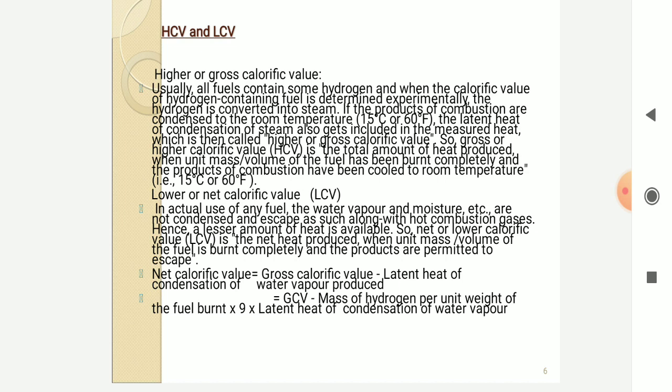The lower or net calorific value is the actual usable heat when water vapors and moisture content are not condensed and escape along with hot combustion gases. Hence, less heat is available. The net lower calorific value is the net heat produced when unit mass of fuel is burned completely and the products are permitted to escape. Net calorific value equals gross calorific value minus the latent heat of water vapor produced, that is: LCV = HCV − (mass of hydrogen per unit weight of fuel × 9 × latent heat of condensation of water vapor).